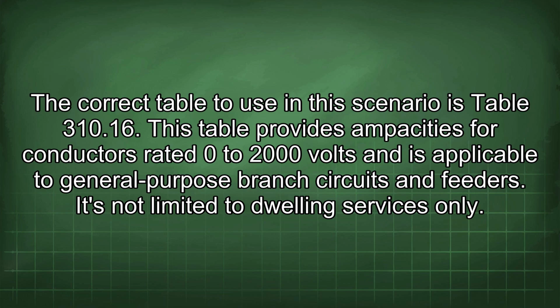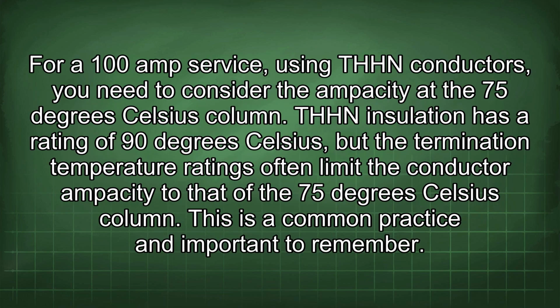This table provides ampacities for conductors rated 0 to 2000 volts and is applicable to general-purpose branch circuits and feeders. It's not limited to dwelling services only. For a 100 amp service, using THHN conductors, you need to consider the ampacity at the 75 degrees Celsius column. THHN insulation has a rating of 90 degrees Celsius, but the termination temperature ratings often limit the conductor ampacity to that of the 75 degrees Celsius column. This is a common practice and important to remember.